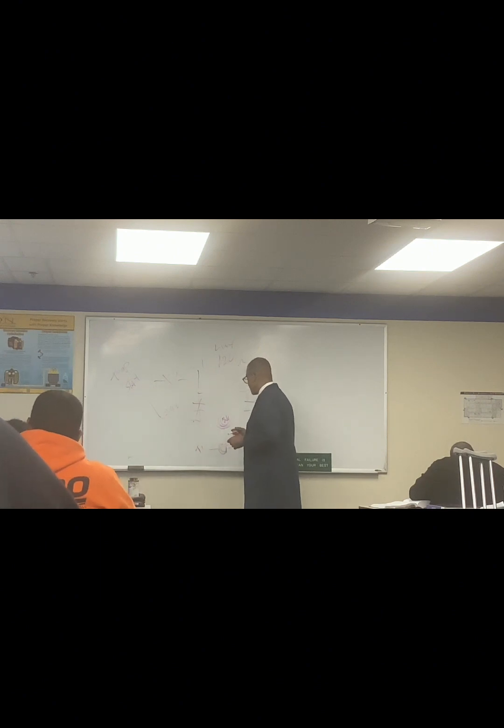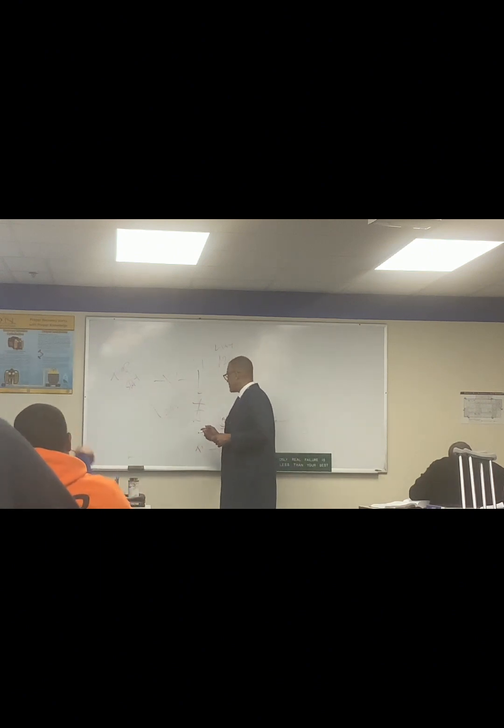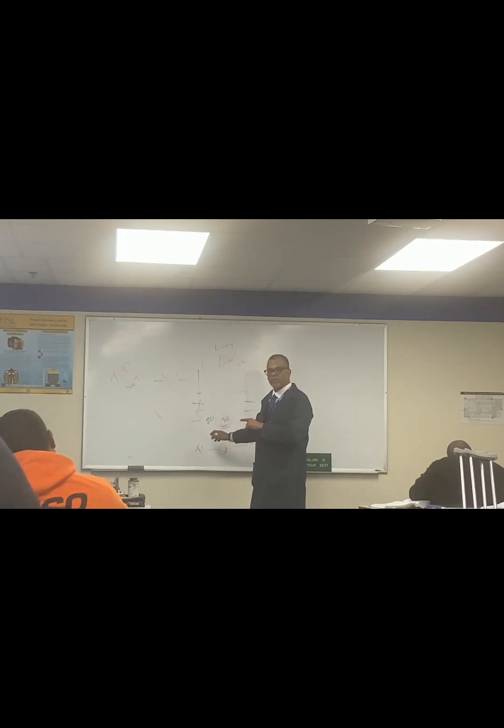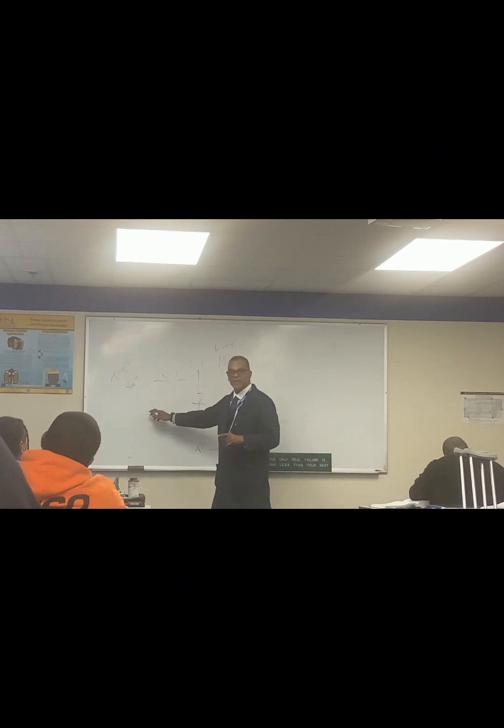By that, we want to be able to understand the series. That is a good question as well, because the series would be that's the 24 volts. The series is in between the contactor coil and the thermostat. So the series would be high pressure, low pressure, for instance, right?